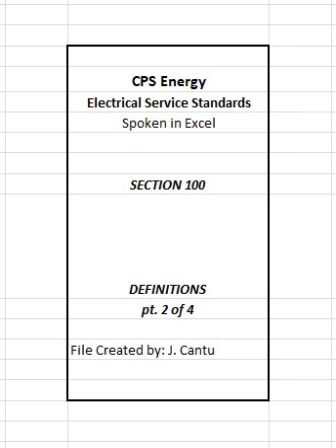Metering equipment rack, meter rack. A freestanding structure used to support metering and service equipment. Typically, a meter rack consists of a minimum of 2-inch rigid capped pipes set in 2 feet of concrete with a minimum of 2 horizontal members. However, size and number of rigid capped pipes and number of horizontal supports will depend on equipment to be supported and length of structure, refer to figure 1820.